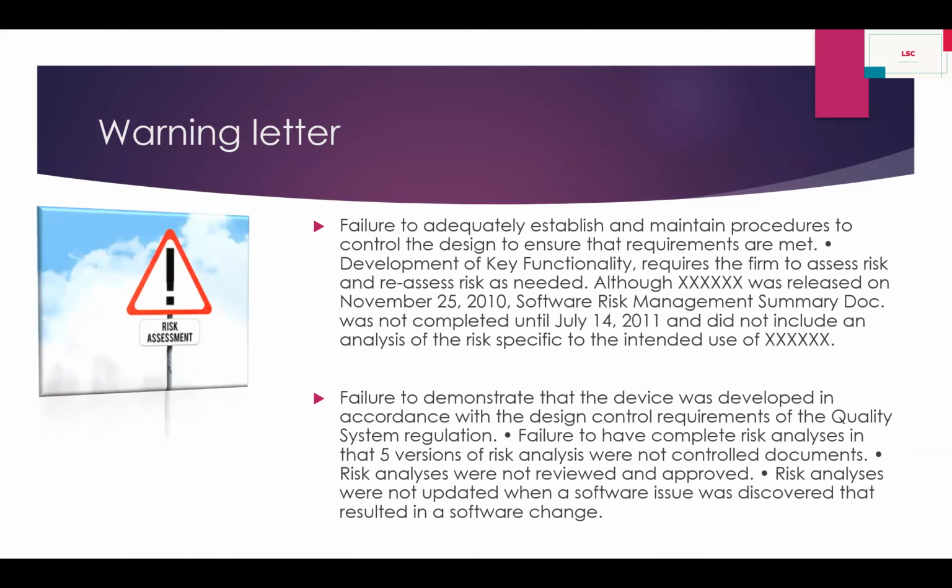Failure to adequately establish and maintain procedures to control the design to ensure that requirements are met. Development of key functionality required the firm to assess risks and reassess risks as needed. Although the software was released in November 2010, the software risk management summary document was not completed until 2011 and did not include an analysis of the risks specific to intended use.